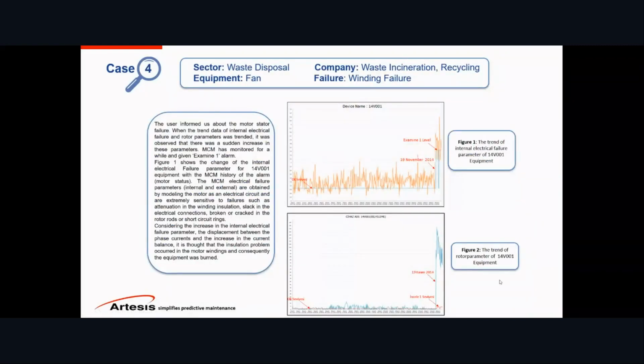And finally, we have here a winding failure. This was an interesting case because actually the equipment failed and it burned. But when the user got in touch with us and asked about this, they realized that the system was warning them already for quite a long time, and it was given an alarm, which sounded, a red alarm basically. But they didn't take action on time, so it actually failed.